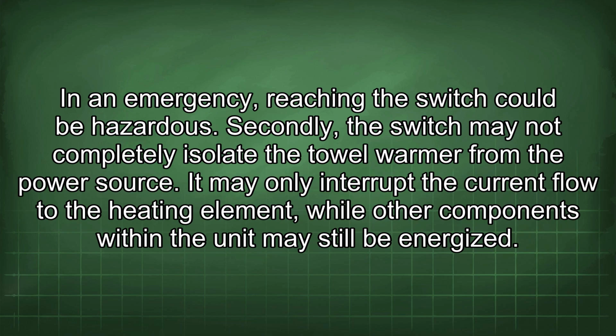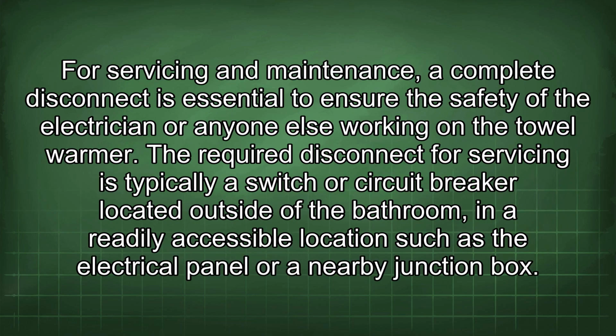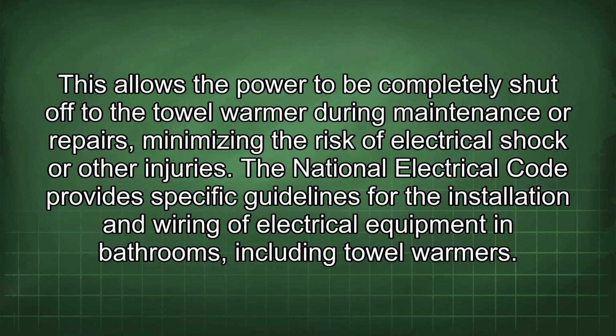Secondly, the switch may not completely isolate the towel warmer from the power source. It may only interrupt the current flow to the heating element, while other components within the unit may still be energized. For servicing and maintenance, a complete disconnect is essential to ensure the safety of the electrician or anyone else working on the towel warmer. The required disconnect for servicing is typically a switch or circuit breaker located outside of the bathroom in a readily accessible location such as the electrical panel or a nearby junction box. This allows the power to be completely shut off to the towel warmer during maintenance or repairs, minimizing the risk of electrical shock or other injuries.